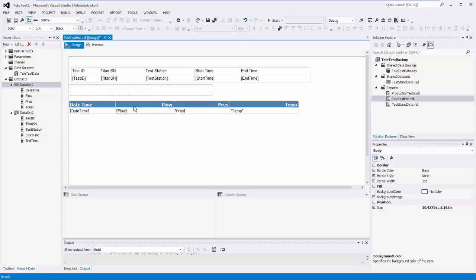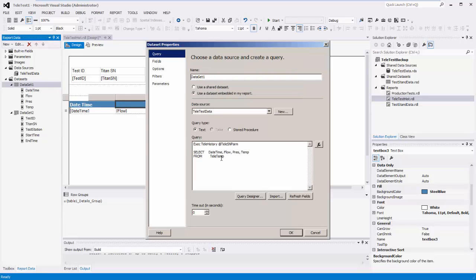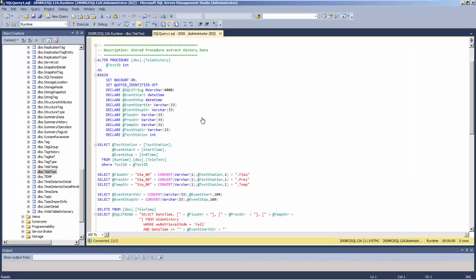This section of the report is used to actually extract the process data — flows, pressures, and temperatures — from the Wonderware Historian. This uses dataset number one. When dataset number one fires, it executes a stored procedure called telehistory, passing in the serial number so the stored procedure knows what data to extract. It then retrieves the flow, pressure, and temperature from that stored procedure and displays them on the report.